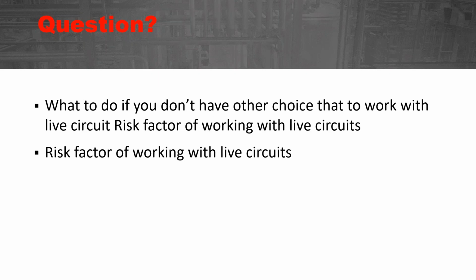I think, again, this is for you, Charlie. What to do if you don't have other choice than to work with live circuits, risk factor of working with live circuits? That's a question. All right. This is a huge, it could be a long drawn out question, but let me point you to the right area. And we talked about it a little while ago. 130 in 70E, 130.2A talks about and covers energized work. And so getting down to the point, if you are working on something that is energized, then the employer is going to have to demonstrate or prove that it's okay to work on that energized.